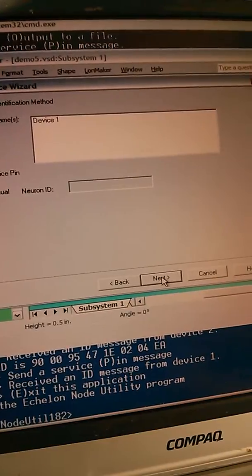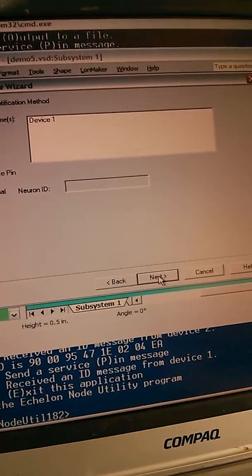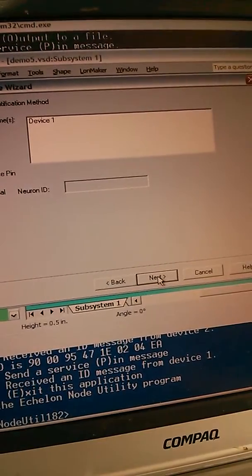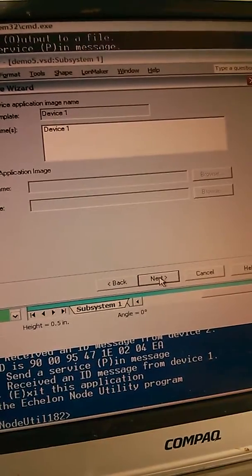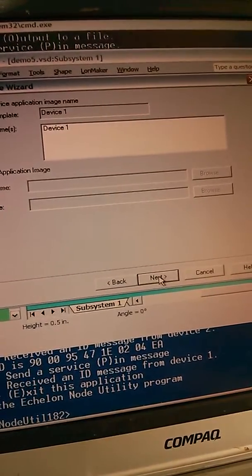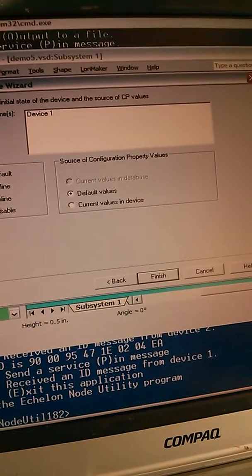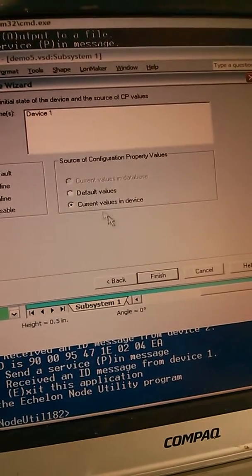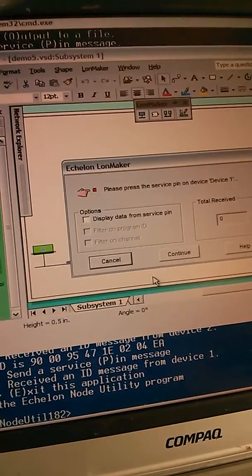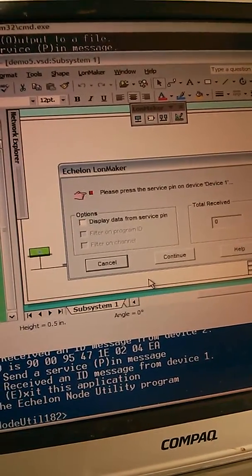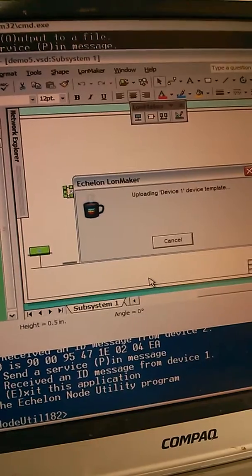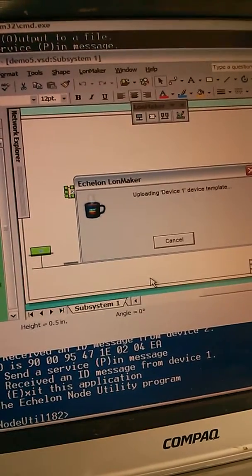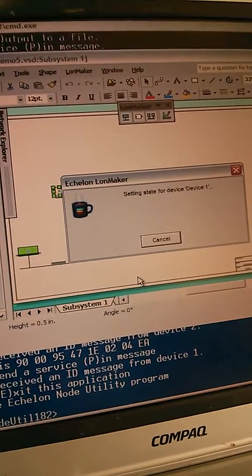And I'm going to commission using the service pin. You could also commission by typing in the Neuron ID if you knew it. Now it's waiting for me to push the service pin. I pushed it. It recognizes it and it's sucking some data out of the device.